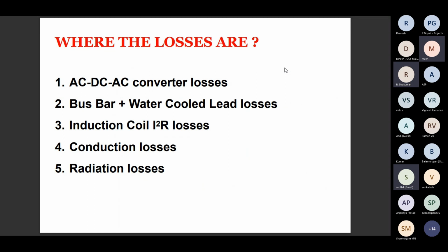So where are the losses in the induction furnace? AC to DC, again DC to AC converter loss, bus bar losses, water cooled lead losses, induction coil I square R losses, conduction losses, radiation losses. The first one is AC to DC, again DC to AC. Normally all the induction furnaces are operated at a voltage of 575 volt. So you need a separate dedicated transformer for the furnace itself.